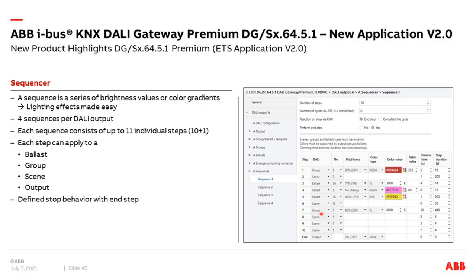In each sequencer step you can assign a group (e.g., group 6), a scene (e.g., scene 3), a ballast (e.g., ballast address 36), or the complete output. You can enter the brightness value, and if it's a color device type 8, you can click to open a color picker and select the color (e.g., yellow or purple), or enter the color temperature (e.g., 3000 Kelvin warm white). Another parameter is the dimming time — for example, within 4 seconds ballast 36 reaches 77% brightness at 3000 Kelvin.